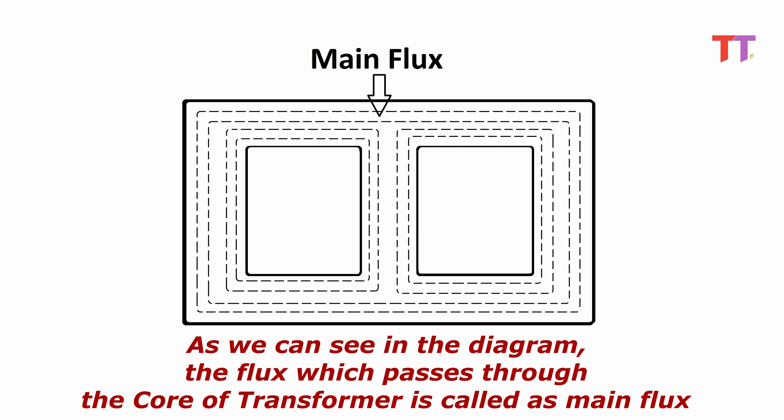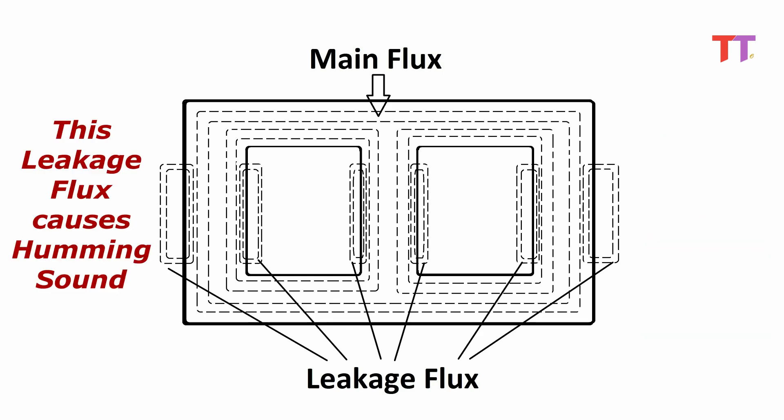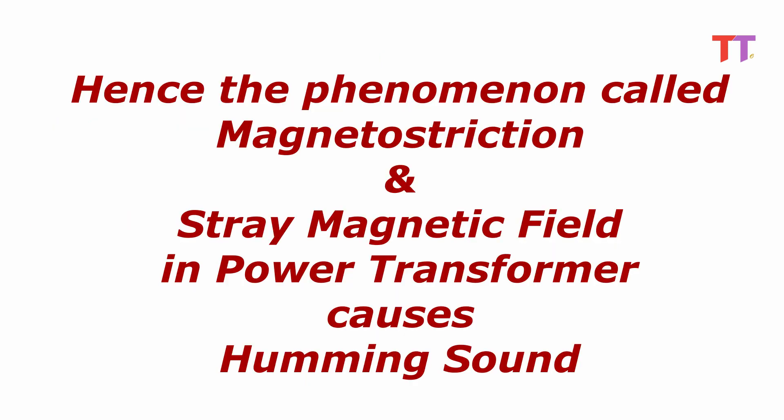As we can see in the diagram, the flux which passes through the core of the transformer is called the main flux, and the flux which passes through the winding insulation and transformer insulating oil instead of the core is called the leakage flux. This leakage flux causes humming sound. Hence, the phenomena of magnetostriction and stray magnetic field in a power transformer together cause the humming sound.